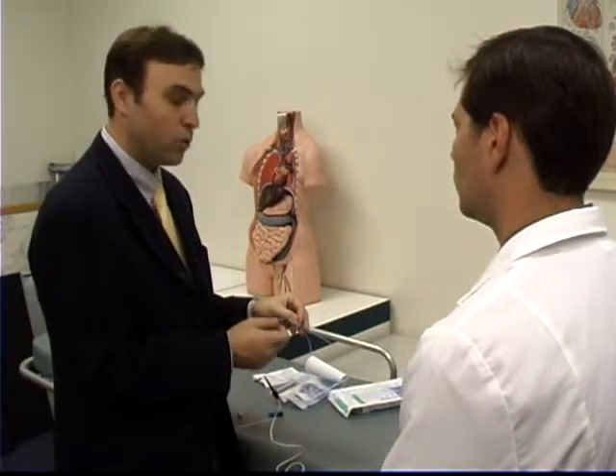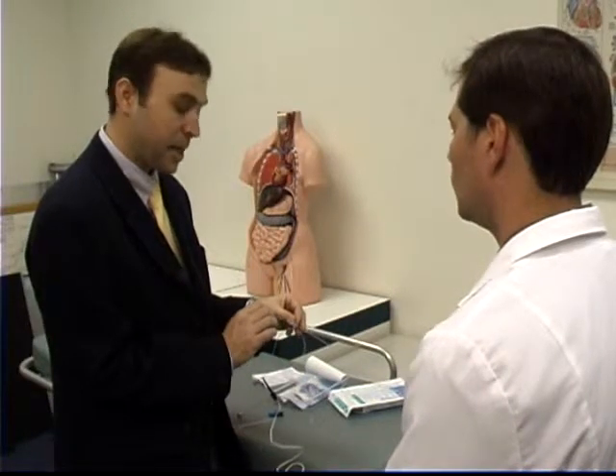I'm really glad that you brought that up, Dr. Spinka. That is one of the major differences between using the StimuCath and doing a single shot procedure or a non-stimulating catheter procedure. If you were to inject your bolus injection through the needle at this point, you would no longer be able to stimulate via the catheter. Whether it's sterile saline or a local anesthetic agent, you disperse the current density at the tip of the needle, and therefore you will no longer be able to stimulate. We don't want to do that because we want to be able to stimulate via the catheter. Does that make sense?